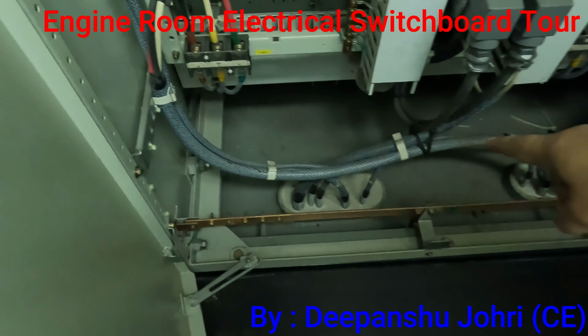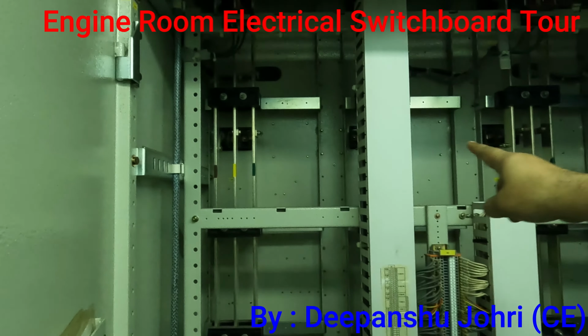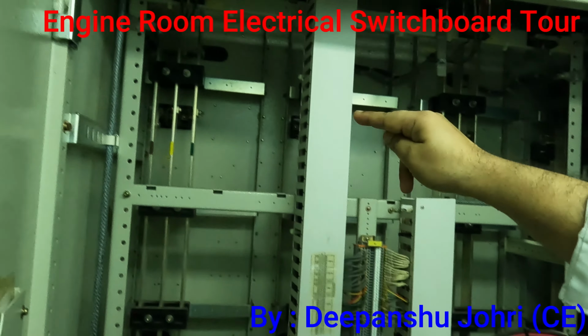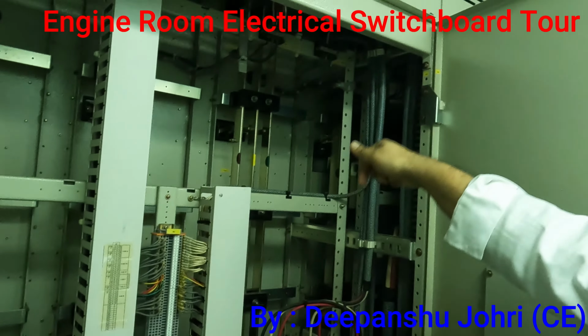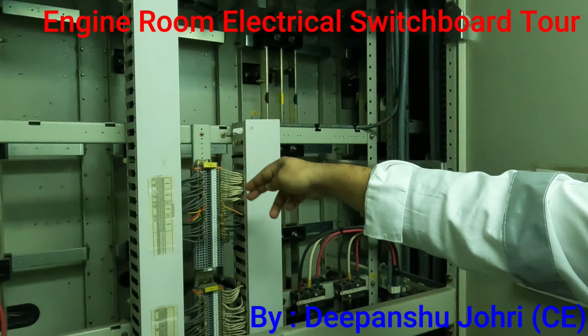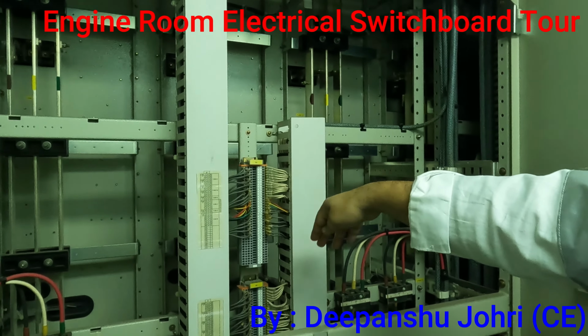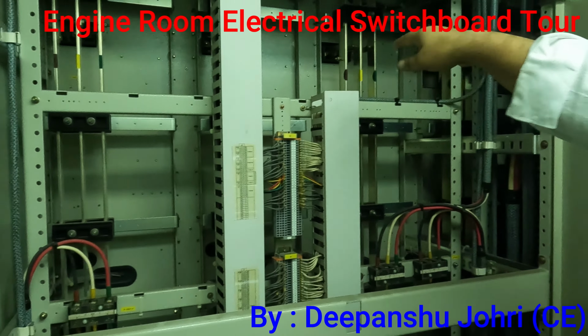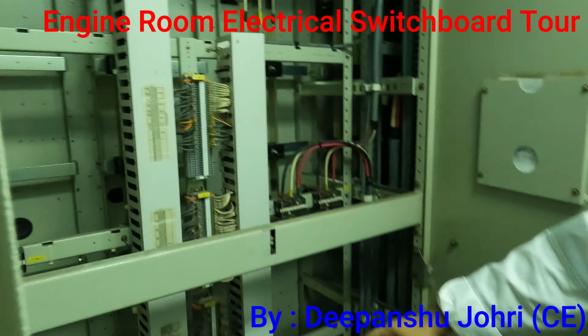This is like your bus bar, 3 RYB, all these bus bars are there, giving 440 supply to each breaker. Breakers are outside, and here you can see the small 24 volt or 220 volt connections going to the auxiliary connections of the contactors.